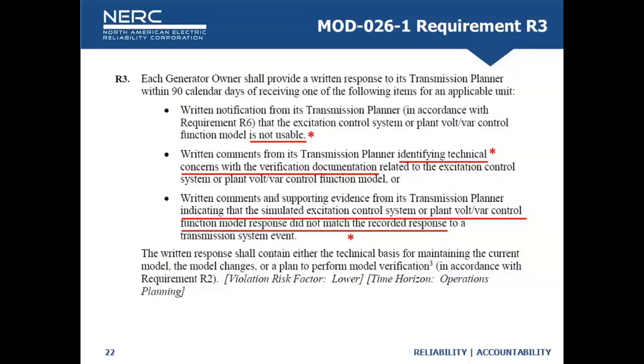You have to help the generator owner get there. They have the data, they want to supply it, but in a lot of cases they just don't know how. Number two: the written comments identifying technical concerns with the verification document. In my opinion, if the documentation is insufficient or leaves gaps, that's a technical concern. If there are errors in the data—if you can look at the reactance values of a synchronous machine and see that they're flipped—that's a technical concern.